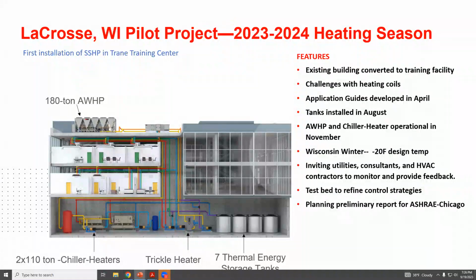Our air source heat pump can operate in cooling or heating. Notice there's no cooling tower on this building, so the air source heat pump operates in cooling during summer. Our two 110-ton chiller heaters just operate as heating products, not cooling chillers, pulling heat from our seven ice tanks to produce heat for the entire building.